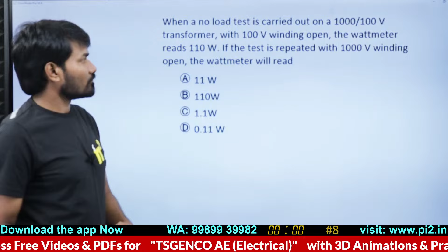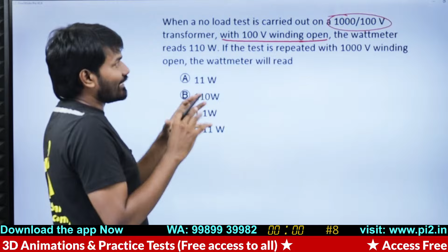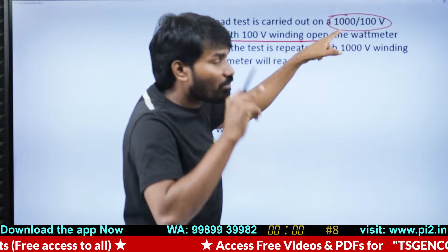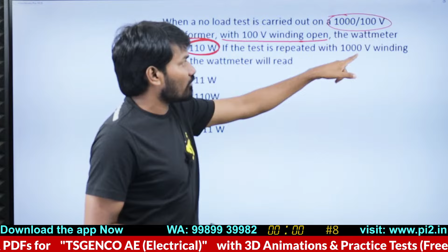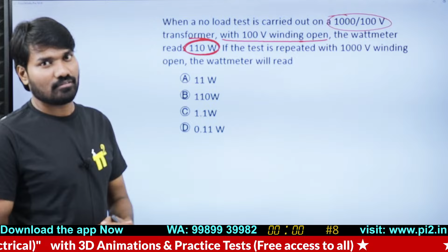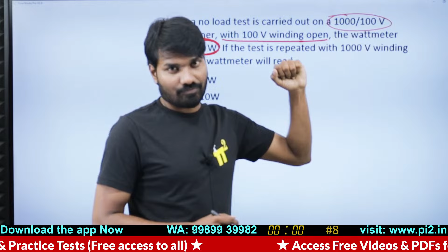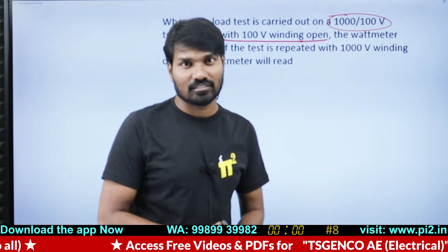You're here to learn. Now, when a no load test is carried out on a 1000 by 100 volts transformer with the 100 volts winding open, you are conducting the no load test, giving supply to the 1000 volts side. Under that condition, the wattmeter shows power losses of 110 watts. If the same test is repeated with the 1000 volts open instead, no crime in that, you can do that. That means you are conducting the test on the low voltage side. What are the power losses then? Same power losses, because it's the same core, same transformer, same rated voltages you are applying. So the answer is the same.